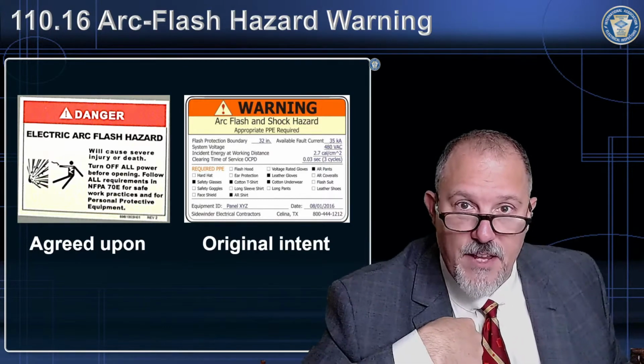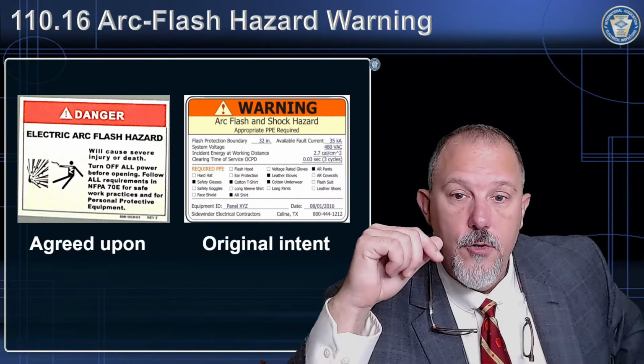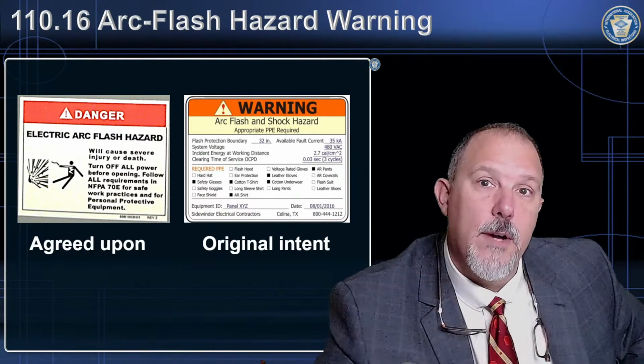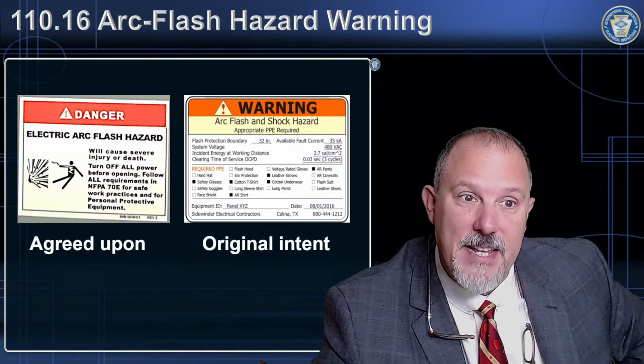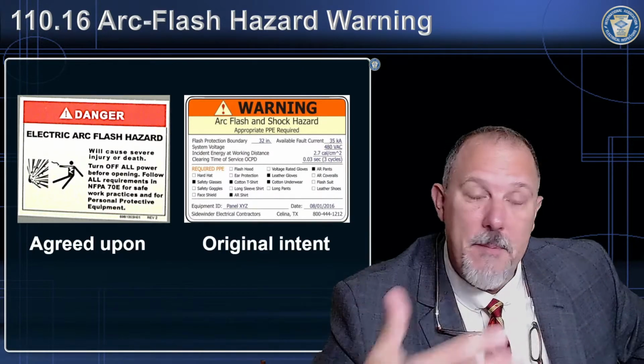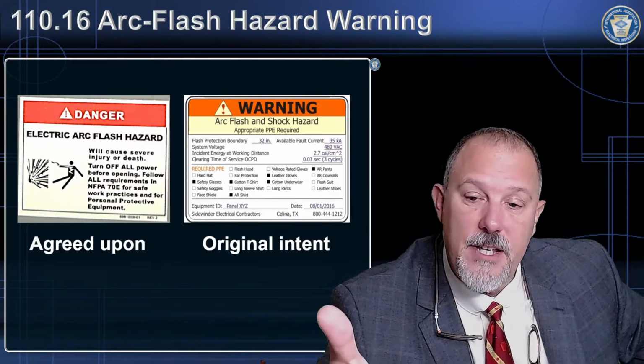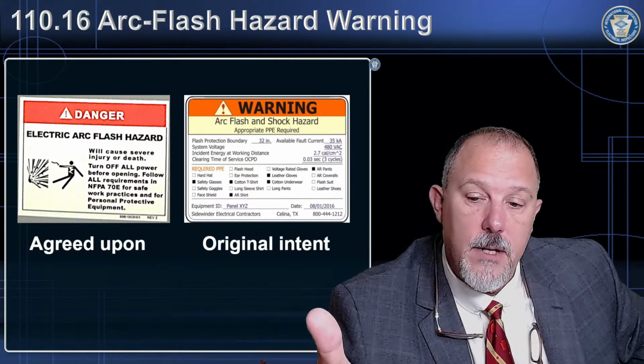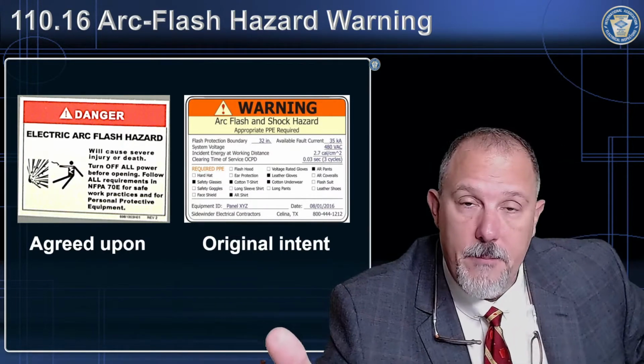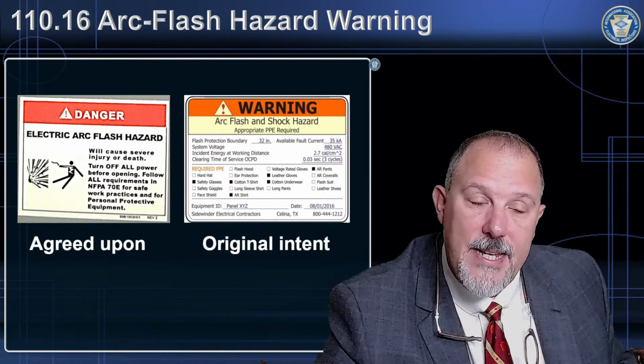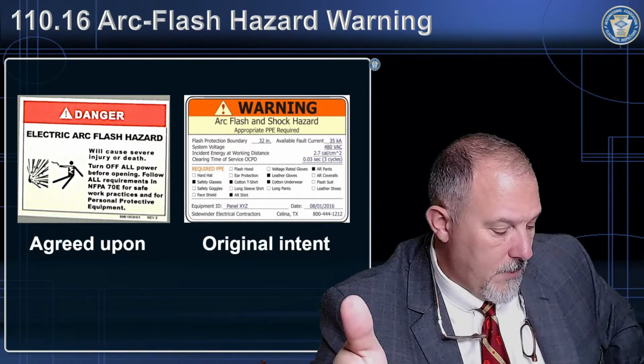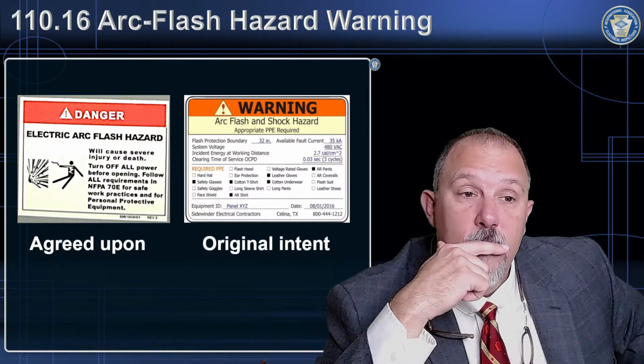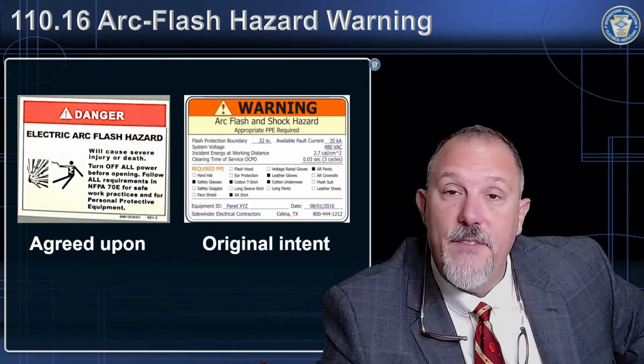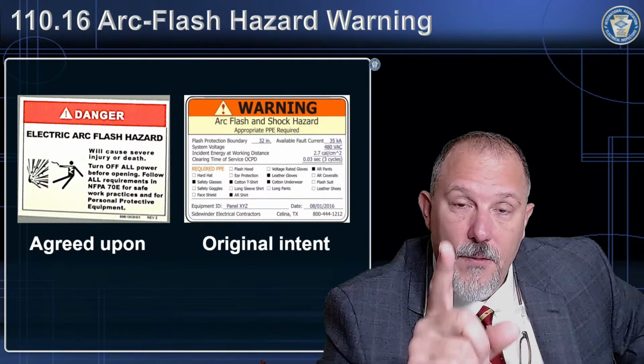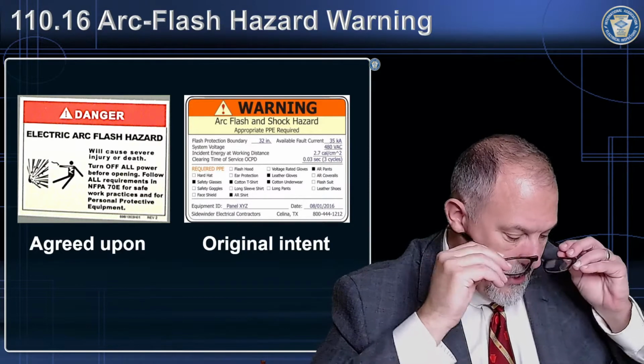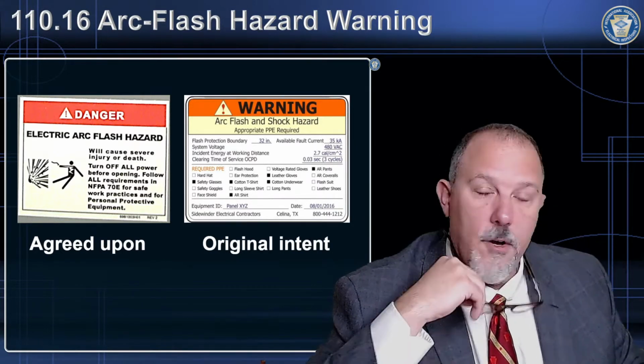That means that I, as a manufacturer, would not be able to put this label on before it left the factory. And this presented a challenge because in many cases, the manufacturer, whether it be Schneider, GE, Siemens, Eaton, whoever else makes equipment of any type that would fall under the requirement 110.16, which would be switchboards, panel boards, and industrial control panels, quite often puts this label on at the factory. But think about what the language says. The language said field marked to warn. So field marked.